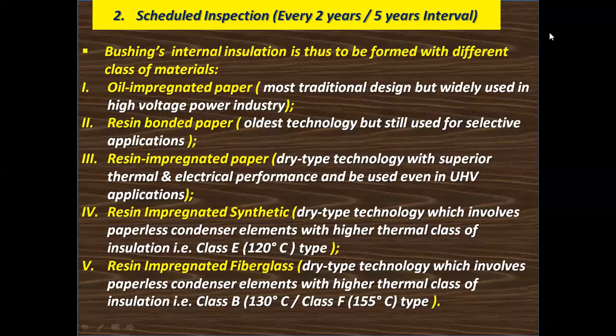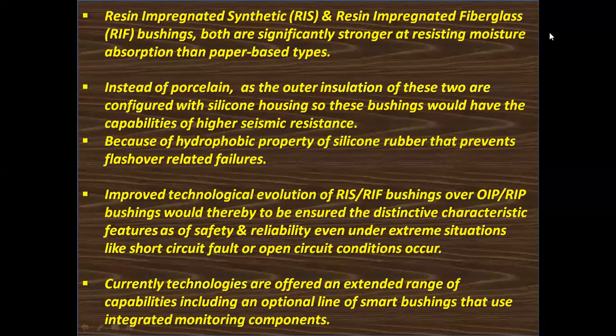Number five, resin impregnated fiberglass, that is dry type technology, which involves paperless condenser elements with higher thermal class of insulation, that is class B insulation, 130 degrees centigrade, and also class F insulation, 155 degrees centigrade type. Resin impregnated synthetic and resin impregnated fiberglass bushings are both significantly stronger at resisting moisture absorption than paper-based types. So, their inspection is something different.